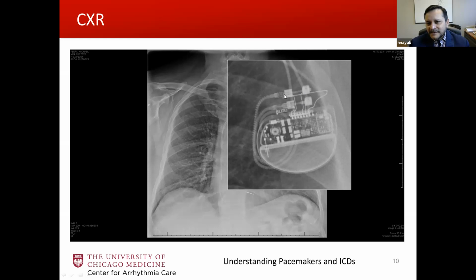Notice that the pacing lead pin is through the distal set screw here in the atrium. You're missing that in the ventricle. So with this person, we talk about a loose set screw. That's certainly one possibility. Or in this case, the pin was just not pushed in past the distal set screw, back in 2011. And the interesting part of this case is that the patient had really no syncope until about 5 years later. Now, remember, he didn't feel just right after pacemaker implant.